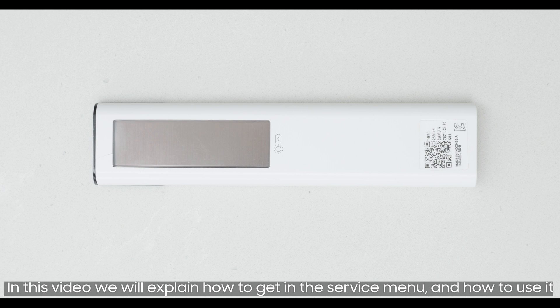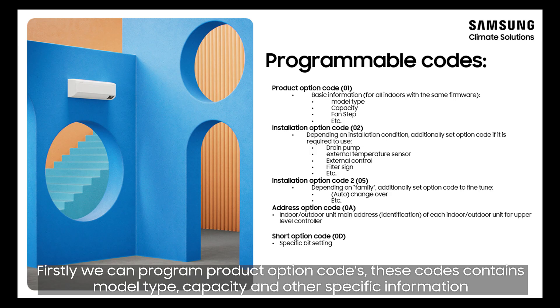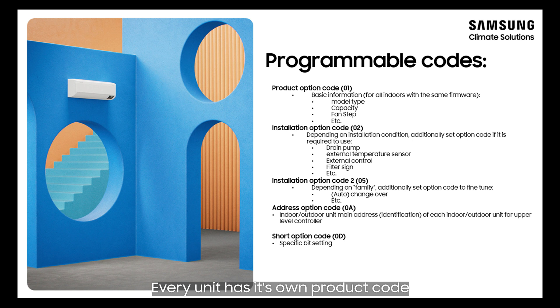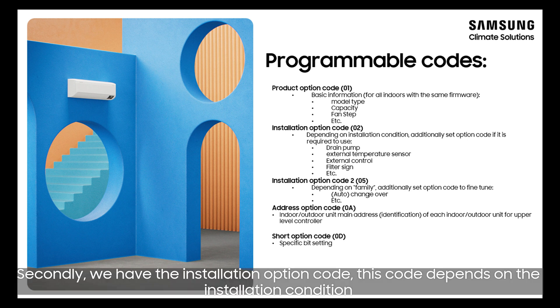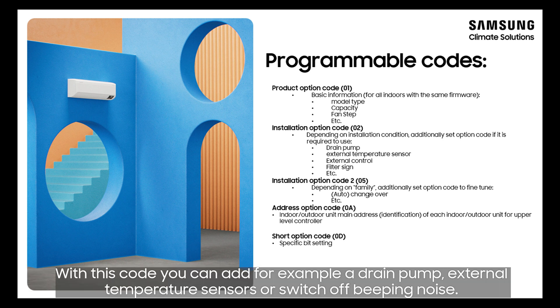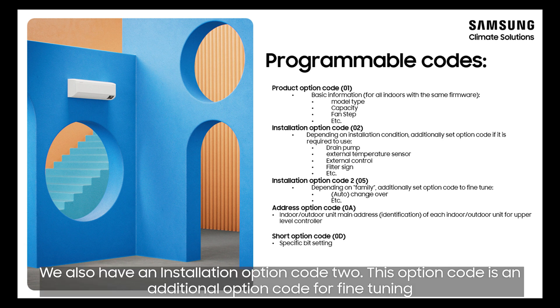In this video we will explain how to get into the service menu and how to use it. Firstly, we can program product option codes — these codes contain model type, capacity, and other specific information. Every unit has its own product code. Secondly, we have the installation option code. This code depends on the installation condition; with this code you can add, for example, a drain pump or external temperature sensors, or switch off beeping noise.